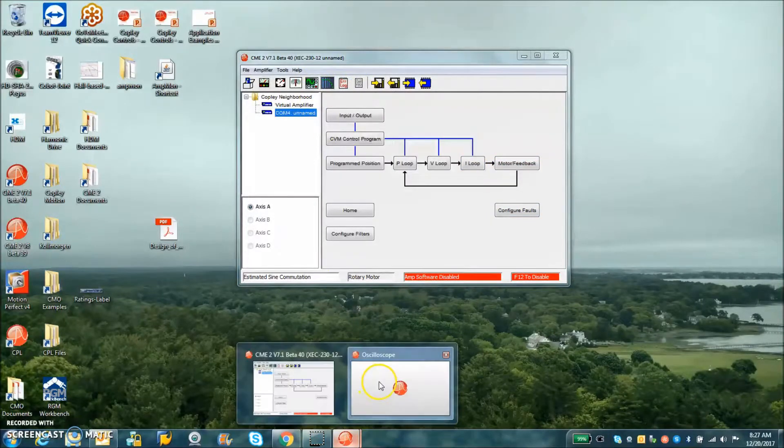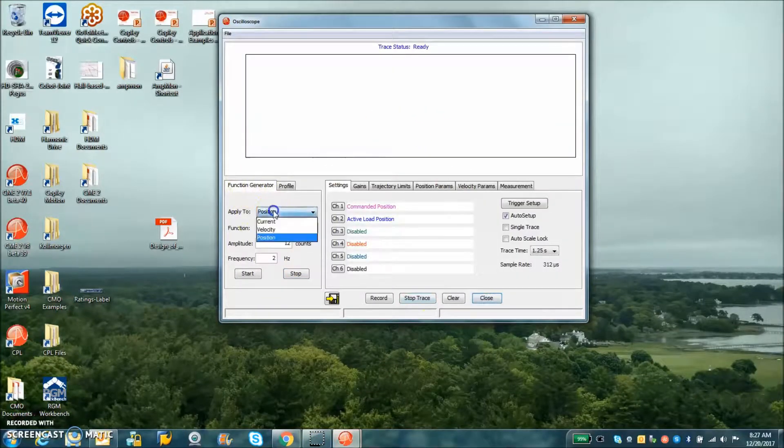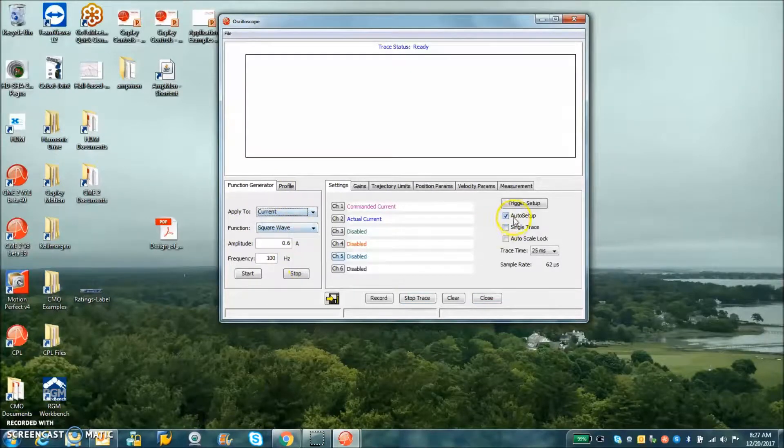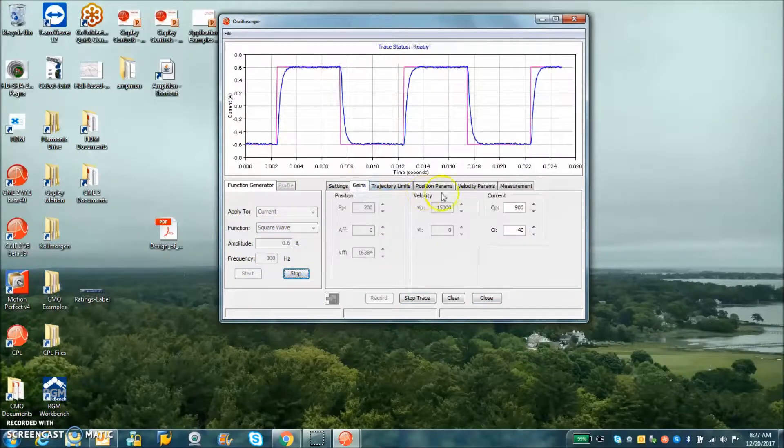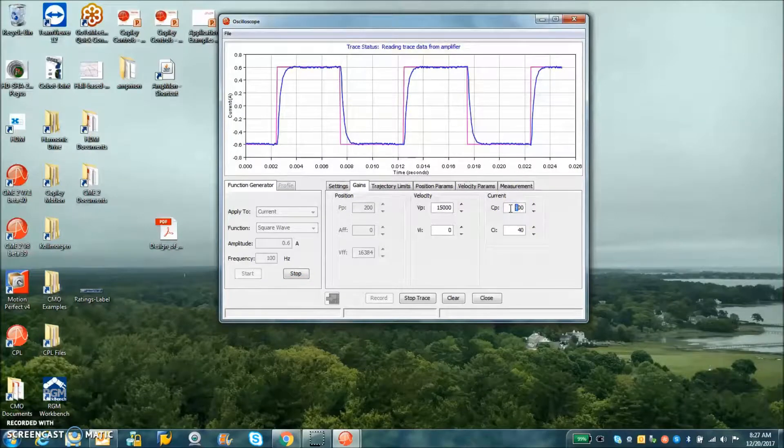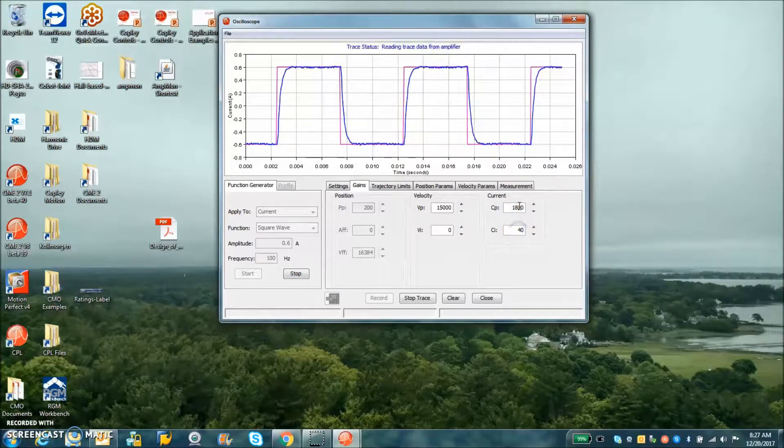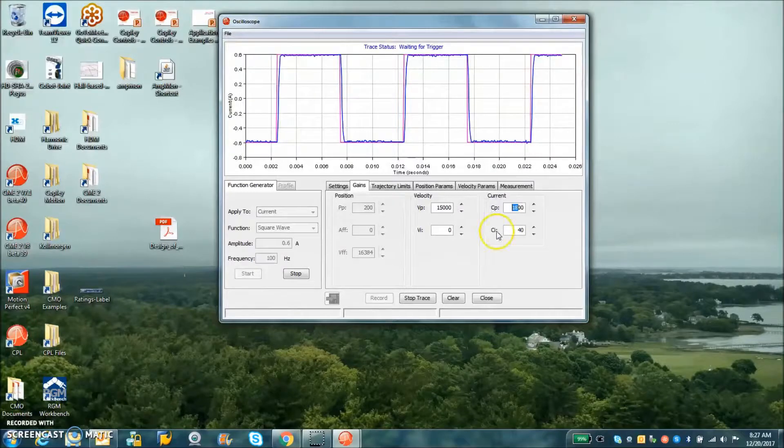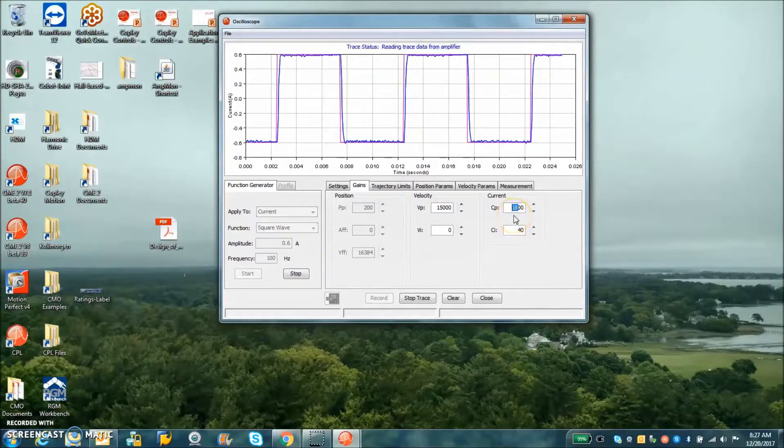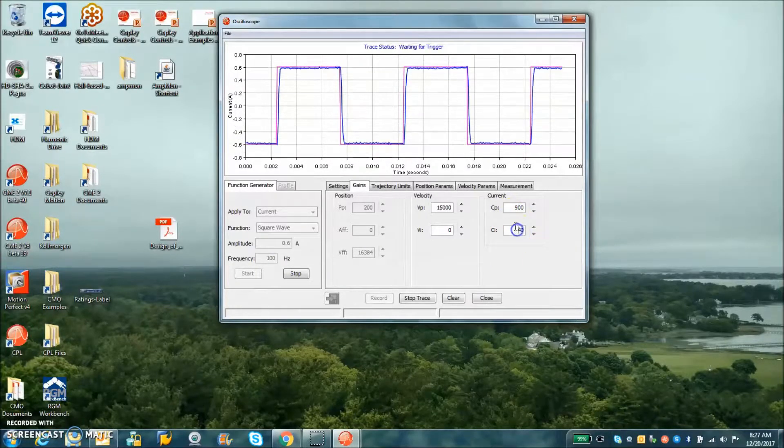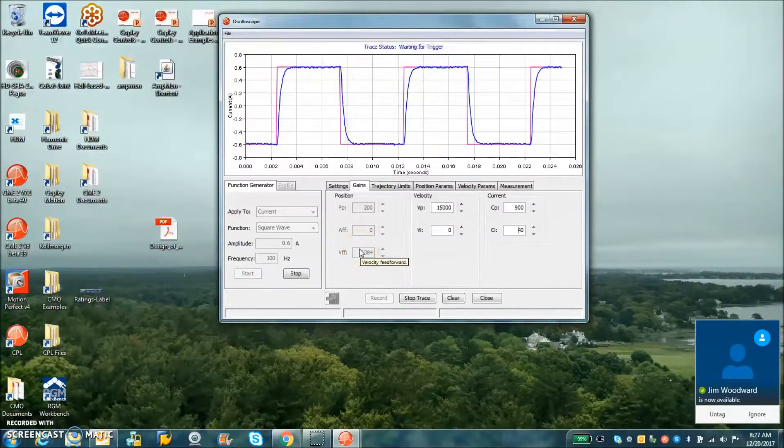The phase commutation is all set and I should be able to do some current loop tuning here. I've got the current set auto setup checkbox, hit start. Of course we can affect the gains, too much overshoot, too ringy. I just gave it kind of critically damped tuning.